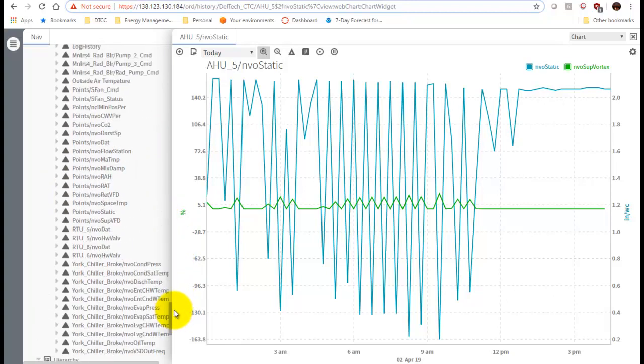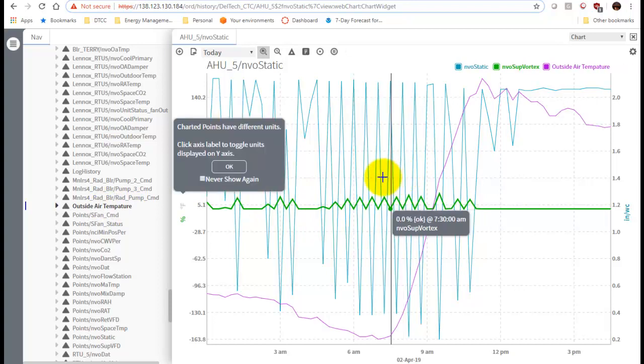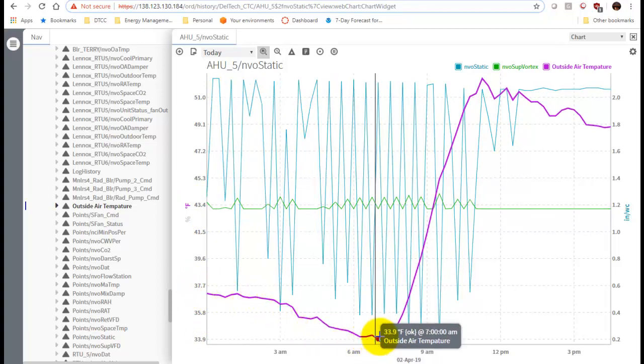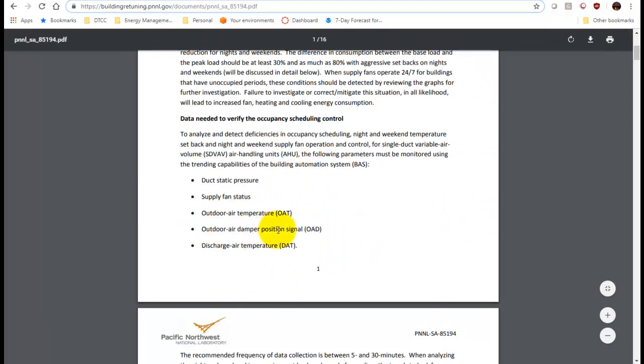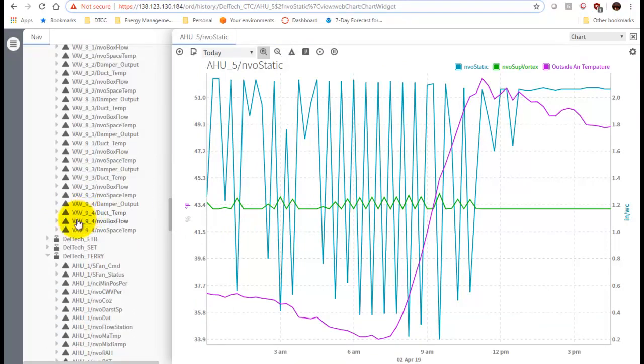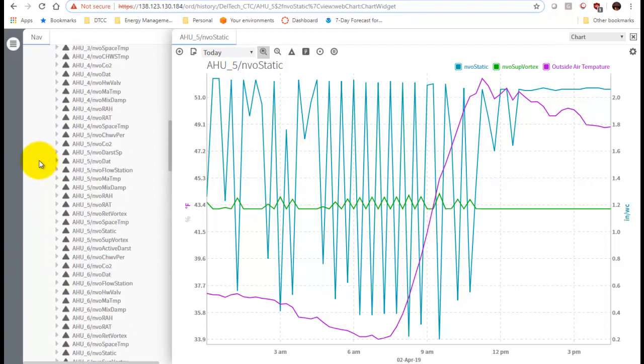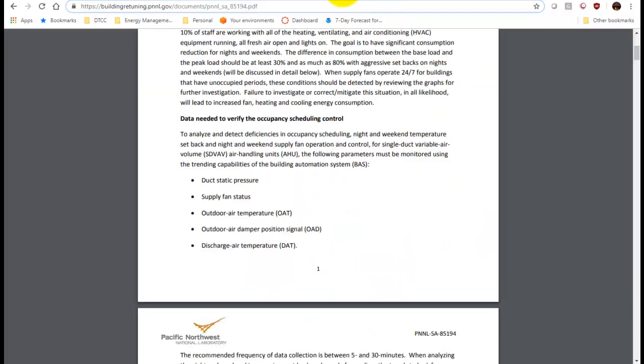So we're going to go down to the Terry building and grab the outside air temperature there. You want to click and drag it over - don't double click because that'll get rid of the data you already have. This gives you a little warning, which is good. The units shown are percentage, but if I click degrees Fahrenheit it gives us the correct temperature profile. Now we have the outdoor air temperature. We can collapse the Terry building and go back to AHU5 to get the outdoor air damper position. The only damper position we have is the mixed air damper, but it's linked to the relief damper and outside air damper, so it's fine to use that one.